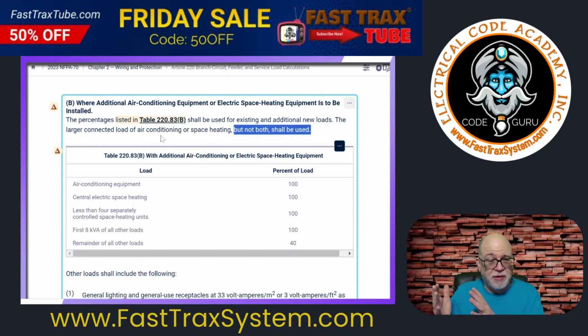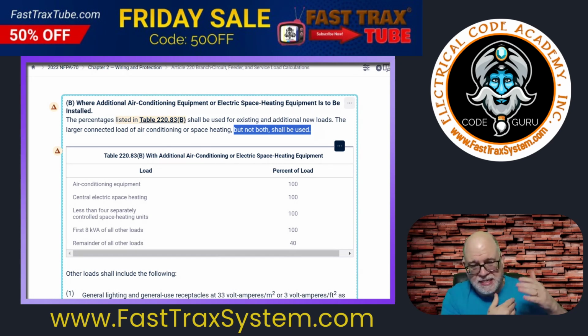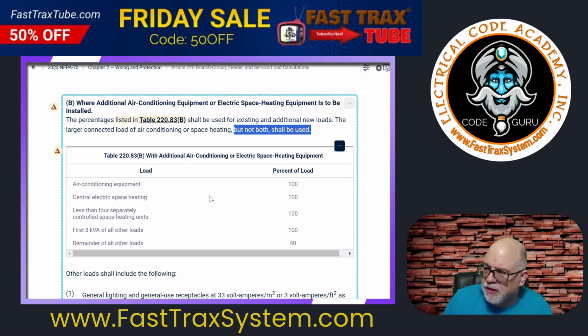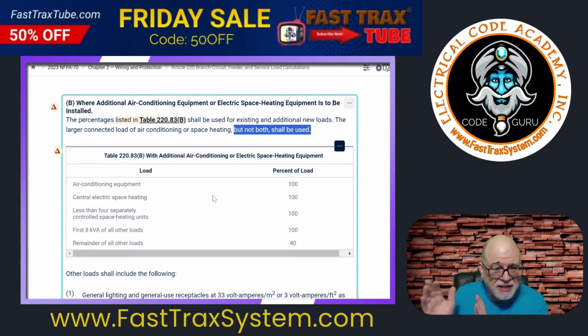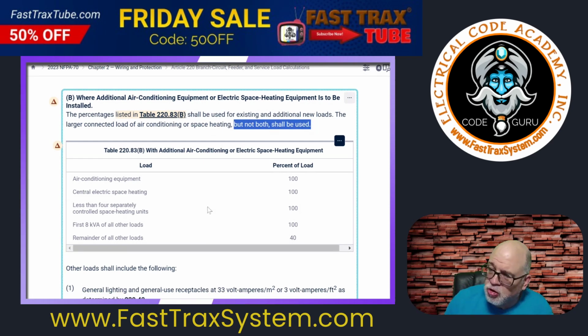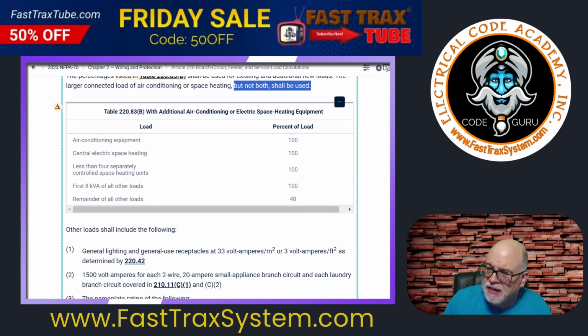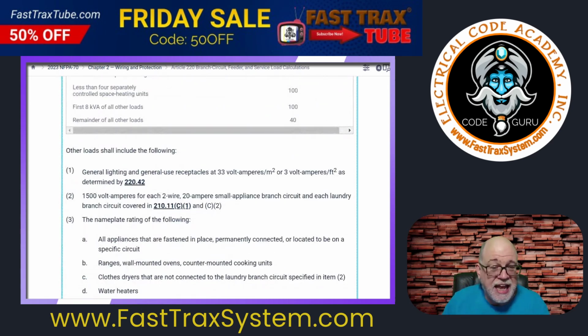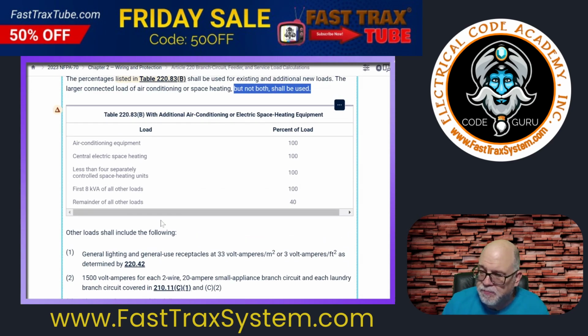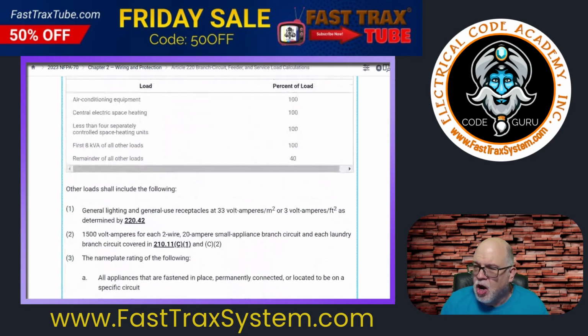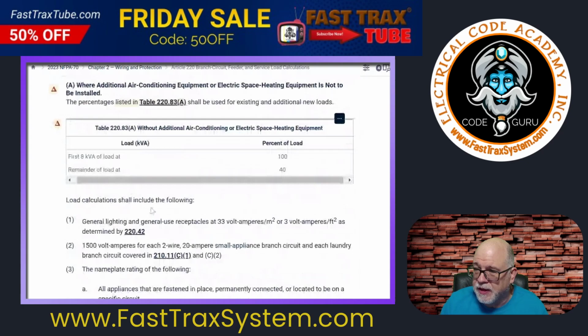Does that seem pretty similar? Right, so that's kind of the same way we do what? When we're doing the optional method where we look for the larger, the heat or the AC, that type of scenario. Same scenario here. Easy thing to remember is heating or air conditioning, they're all just taken at 100%, and whichever is larger, that's the one you take. And you add that to the calculation that you did similar to what we just did in A. There's no difference. It's just now you're adding the additional loads for B, okay? So that's all you're really doing there.